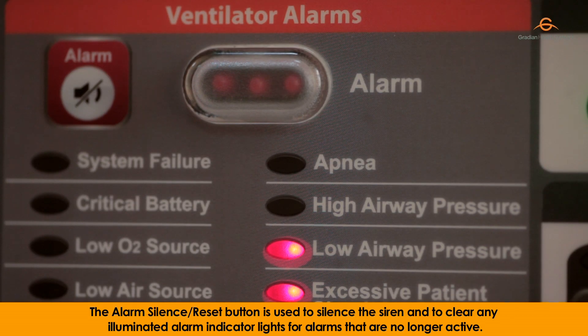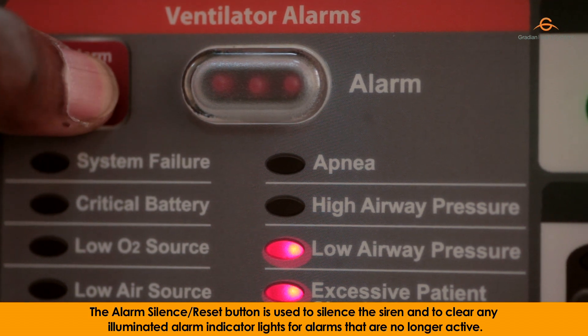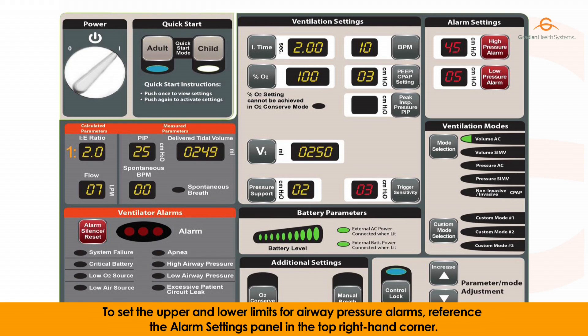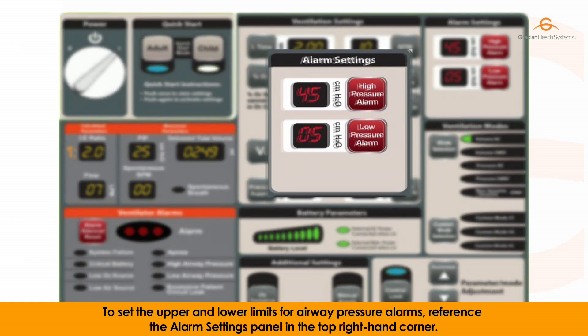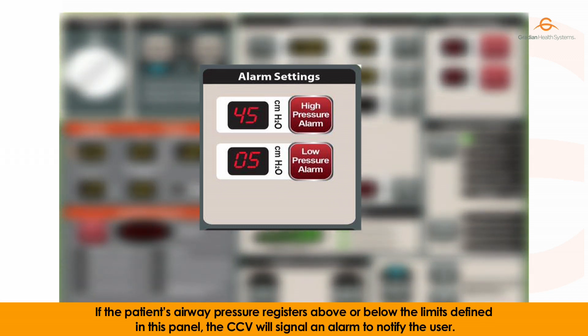This is not the case for the low oxygen and low air source alarms, however, which will fully clear if the gas sources are restored. The alarm silence/reset button is used to silence the siren and to clear any illuminated alarm indicator lights for alarms that are no longer active. To set the upper and lower limits for the airway pressure alarms, reference the alarm settings panel in the top right-hand corner. If the patient's airway pressure registers above or below the limits defined in this panel, the CCV will signal an alarm to notify the user.